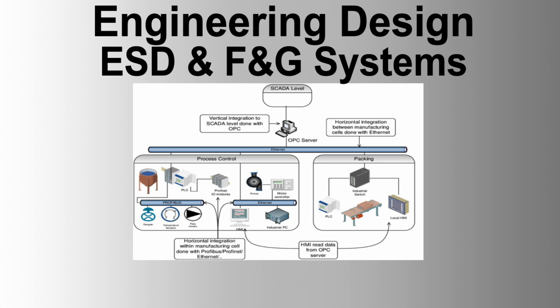Fire and gas system software. 1. Detection and response. The F&G software must monitor fire and gas detectors and initiate appropriate responses. Automated actions include triggering alarms, activating suppression systems, and isolating hazard areas. Interface with fire and gas sensors, ensuring real-time data acquisition and processing.